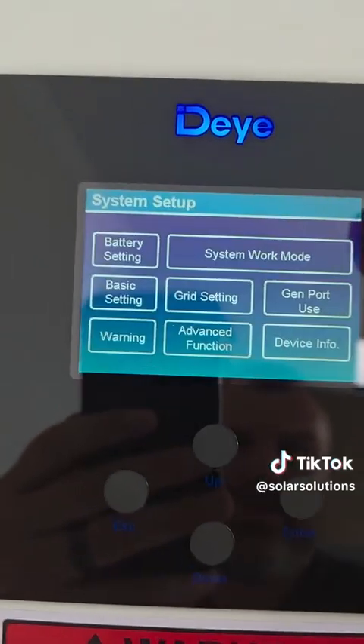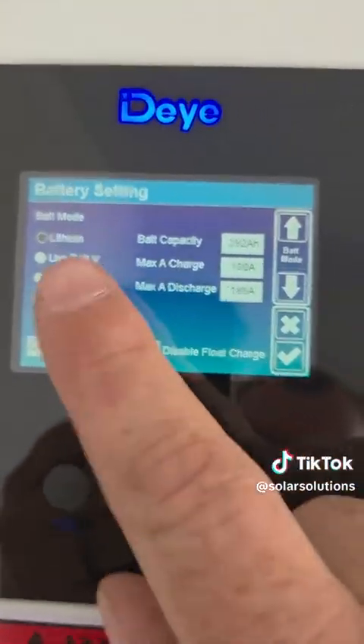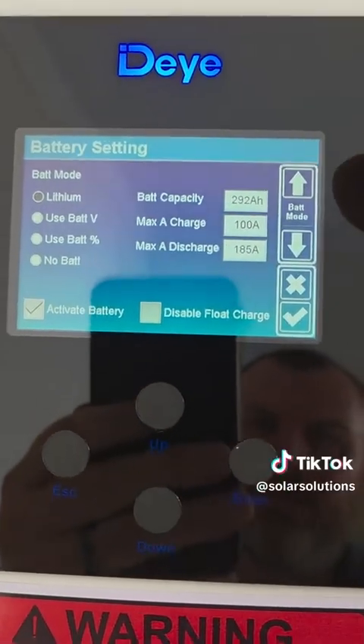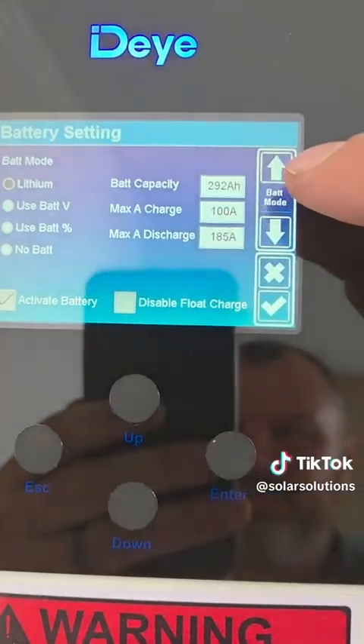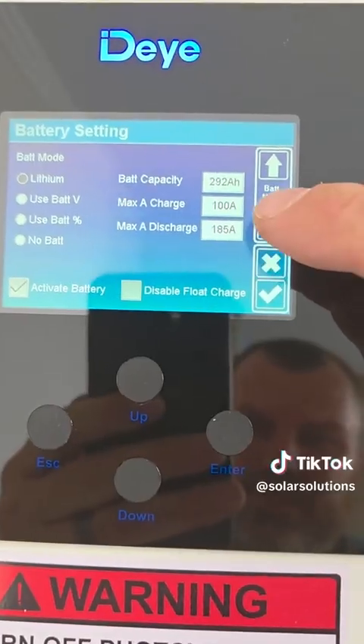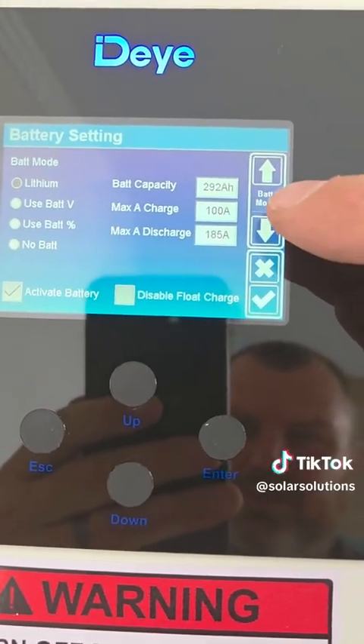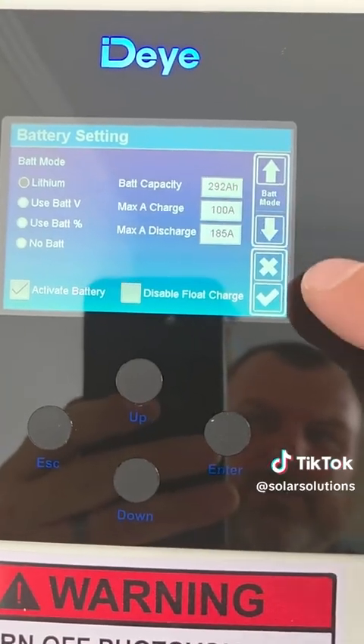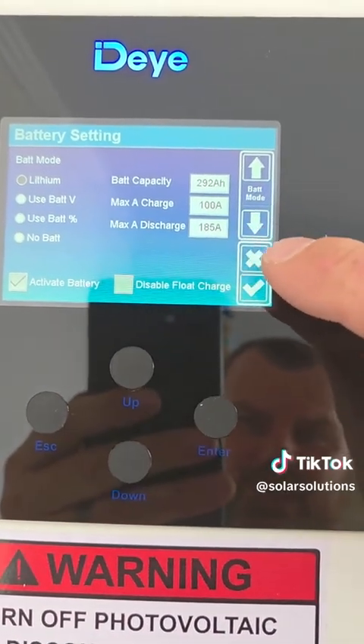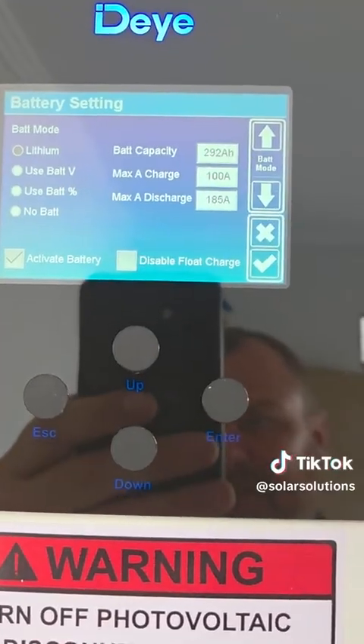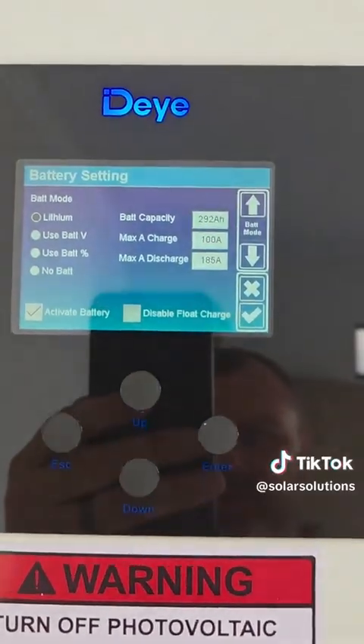Now, just to show you guys a little bit of other things, so on the battery settings, it's normally lithium and it's communicating. So these batteries are about 97 amp-hours per battery. So max charge current is about 100 amps. You can obviously set that faster or slower depending on how aggressive you want to be. And then obviously we can fully discharge 8 kilowatt, which is 185 amps, since our batteries can discharge far more than that as well.